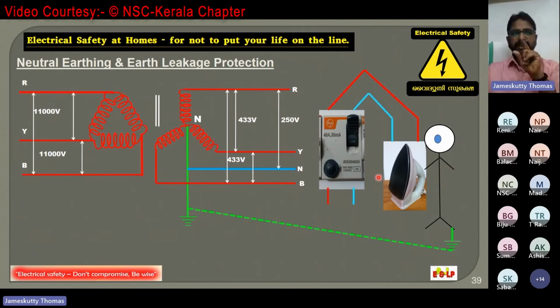Also, please note that if this neutral point is loosely connected, instead of zero potential in the neutral, you will be getting a voltage. It may have some voltage. In our house connection, usually we can check it by measuring the voltage between this neutral and earth. Usually it can be 2 volt or 5 volt, or even 1 volt. If it is beyond these limits, a complaint should be registered to KSEB.